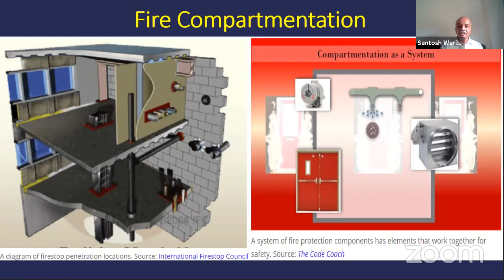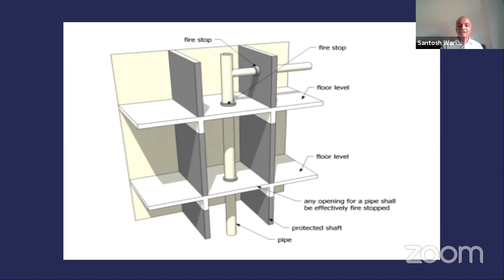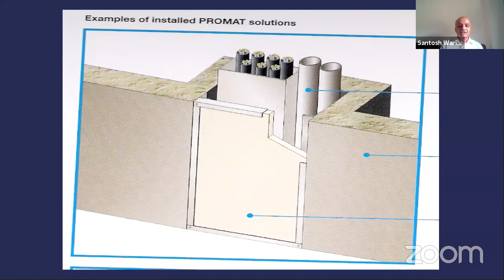So this is an example of how the plumbing is passed through the different compartments horizontally and vertically, and everywhere the fire stops or fire sealants shall be used to contain the fire. In case of fire, this will come into action and it will not allow the fire to spread horizontally and vertically. This is the normal practice used for carrying the electrical cables in high-rise buildings, where you have a separate duct, and in that also you have a bus bar like situation. Different services are passing through the ducts, electrical ones or fiber optic or any IT related things.